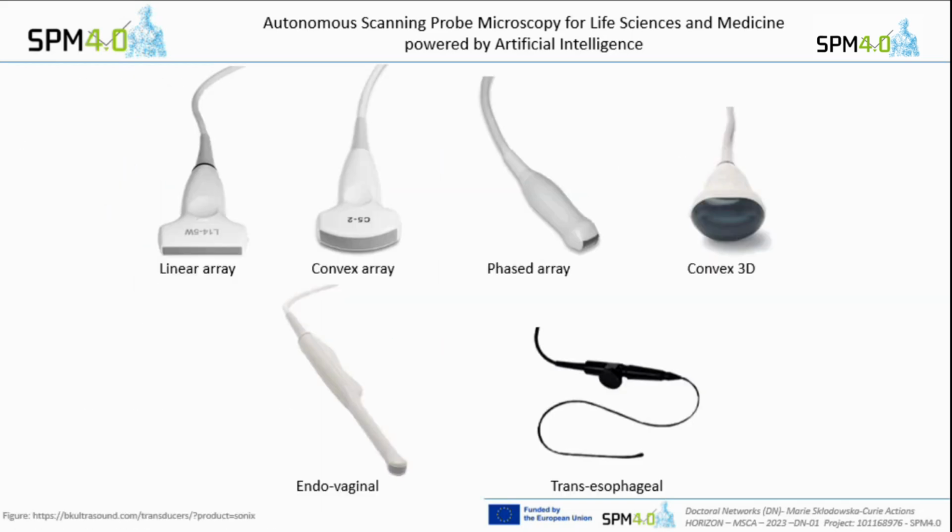This one has a very small footprint. This is the footprint, the gray area, and this is used for cardiac application. Because if you have the ribs here, you can place the transducer along the ribs, but then you're unable to rotate this. And with the phased array, you have a small footprint, you're free to move everything.